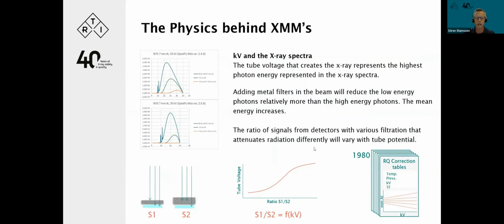Looking a little bit at the physics behind this, we're coming back to 1980 when I said we measured kV. To measure kV is about analyzing and getting information from a spectra, but it is not the entire spectra. kV, tube voltage, is the highest potential that creates the spectra. So one could say we're looking for the absolute rightmost point of the X-ray spectra, where the spectra reaches the y-axis 0.